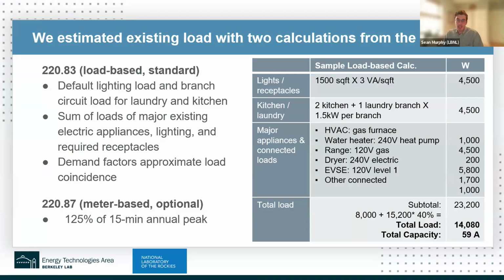As I mentioned earlier, we estimated existing load using two load calculations from the 2023 National Electrical Code. This first method, referred to as Section 220.8.3 or the load-based method, is most common, and it basically tabulates individual loads. It has some default assumptions for the load associated with lighting and branch circuits that serve laundry and kitchens. It also applies demand factors to individual loads, approximating coincidence on a peak day. The code is recognizing that you're not using everything in your home at the same time, and applies this factor to account for the degree of overlap in those loads.